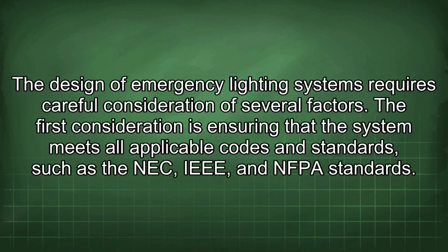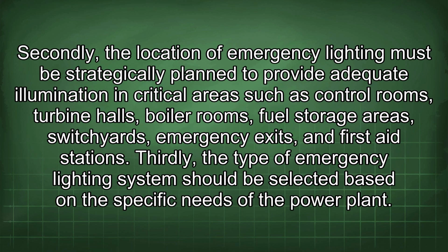The design of emergency lighting systems requires careful consideration of several factors. The first consideration is ensuring that the system meets all applicable codes and standards such as the NEC, IEEE, and NFPA standards. Secondly, the location of emergency lighting must be strategically planned to provide adequate illumination in critical areas such as control rooms, turbine halls, boiler rooms, fuel storage areas, switchyards, emergency exits, and first aid stations.